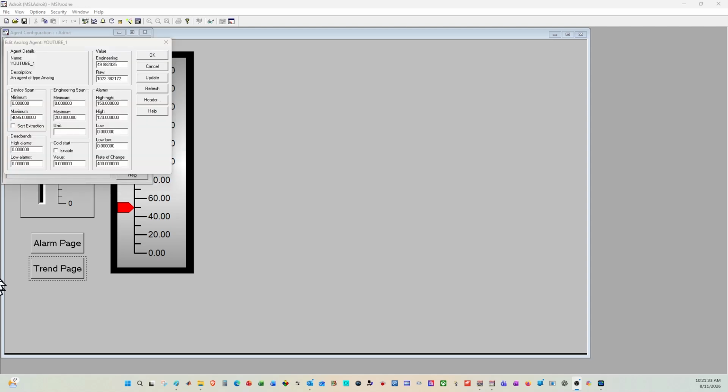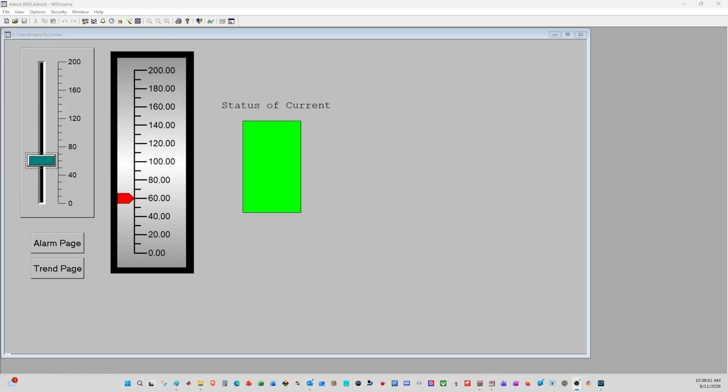So in the long term, what I'm going to do is that any current that is below 120 amps will be displayed as green for the operators. If we exceed 120 but be less than 150, we'll regard that as a high current situation and we'll display that as amber for the operators. And if we were to go above 150, then that might be indicative of a high current situation and we'll display that in red for the operators. And this is exactly what we have done.